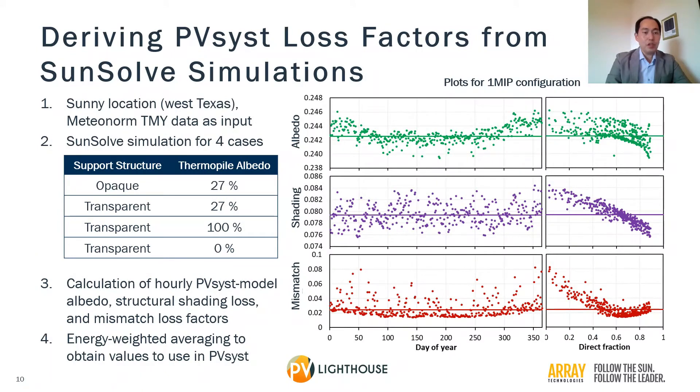To derive PVsyst loss factors to use for bifacial simulations, we ran SunSolve simulations for a West Texas location with different values for the support structure opacity and the albedo as would be measured by thermopile pyranometers. As you see on the plots on the right, the hourly effective albedo, shading loss, and mismatch loss vary over the year with strong dependence on what fraction of the irradiance comes from the beam component. By doing an energy-weighted averaging, we obtain loss factor values to use in PVsyst to get matching results for the annual energy production. Keith McIntosh of PV Lighthouse is presenting this methodology separately at this virtual bifacial PV workshop, and I strongly recommend this presentation to the audience.